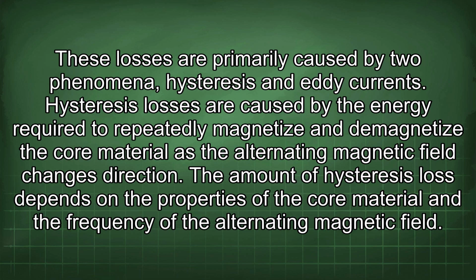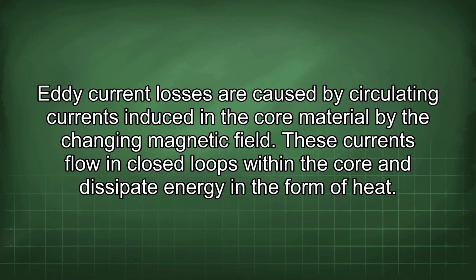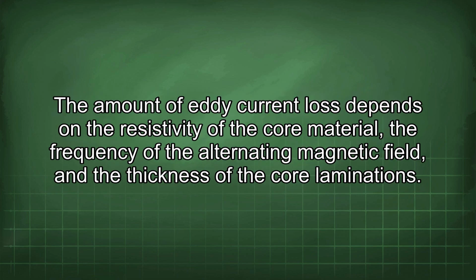Eddy current losses are caused by circulating currents induced in the core material by the changing magnetic field. These currents flow in closed loops within the core and dissipate energy in the form of heat. The amount of eddy current loss depends on the resistivity of the core material, the frequency of the alternating magnetic field, and the thickness of the core laminations.